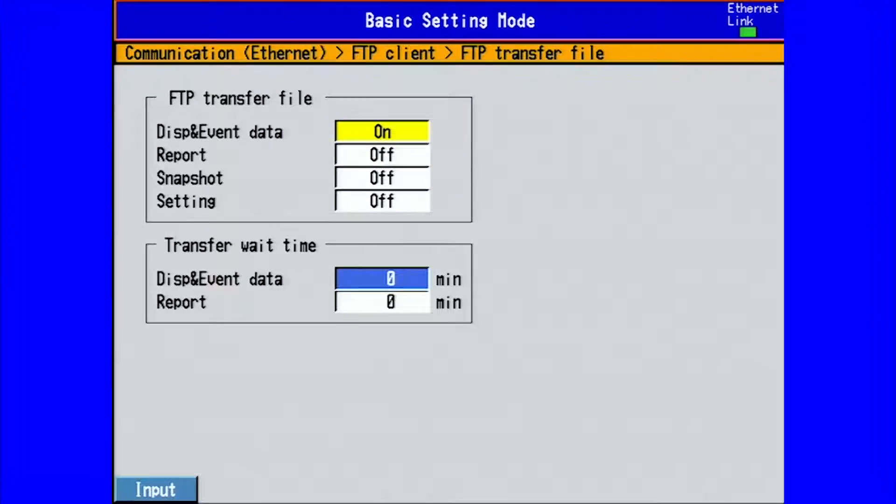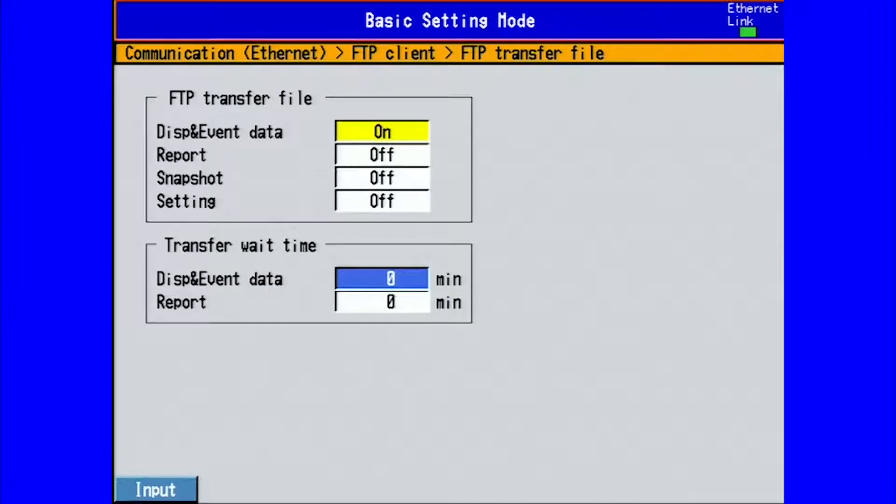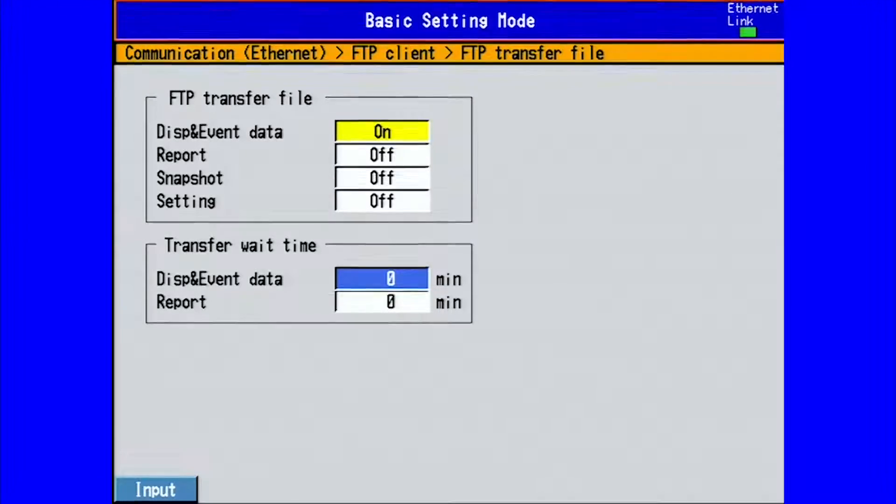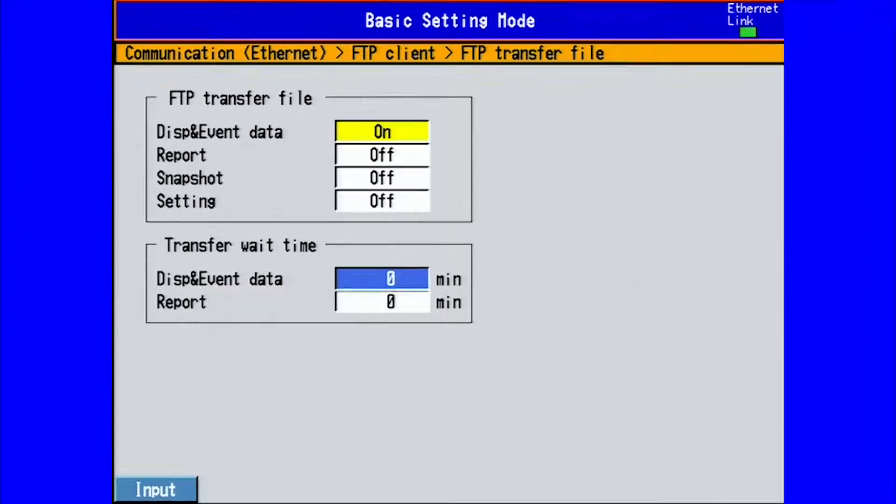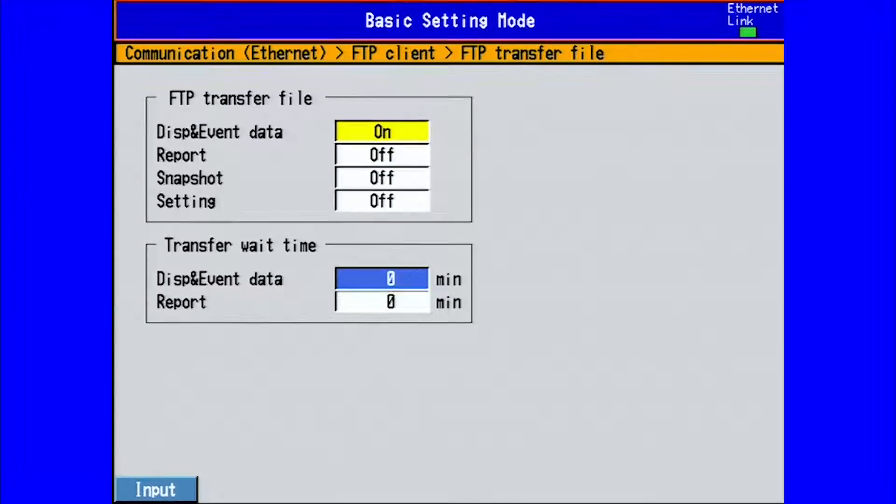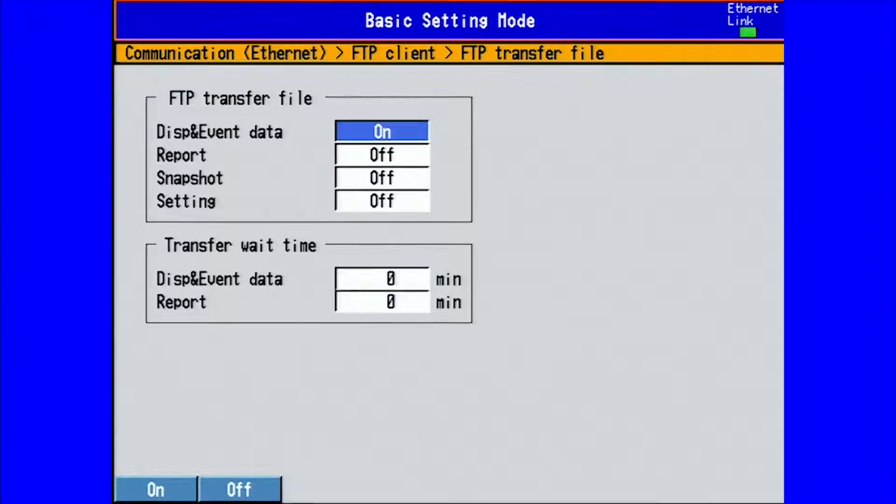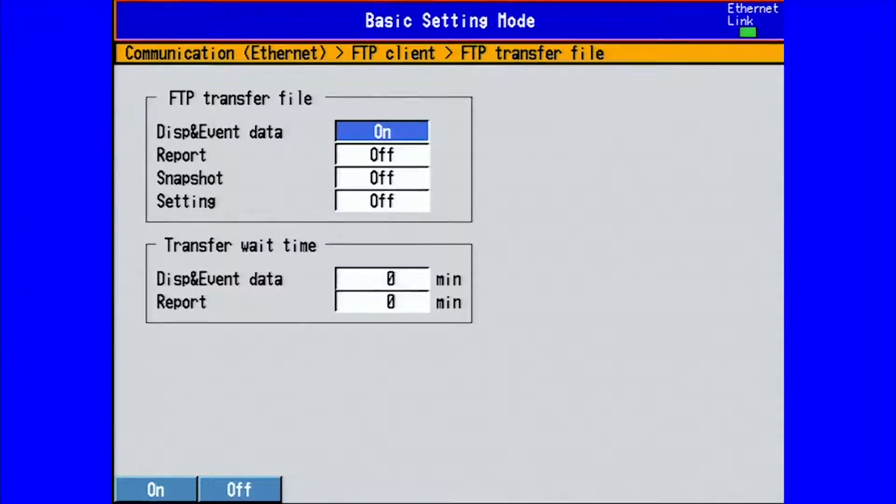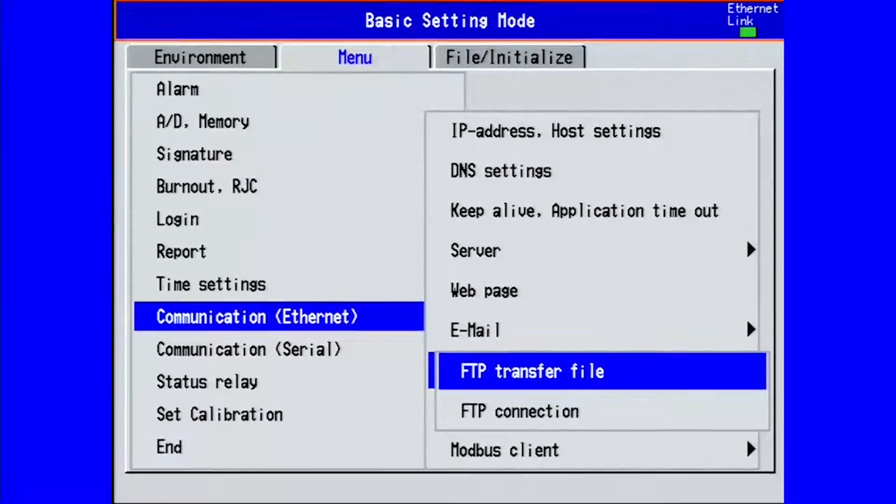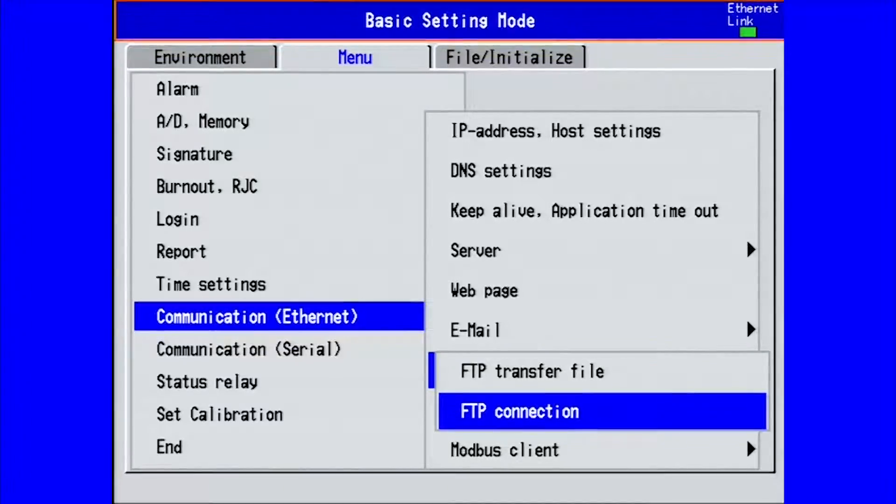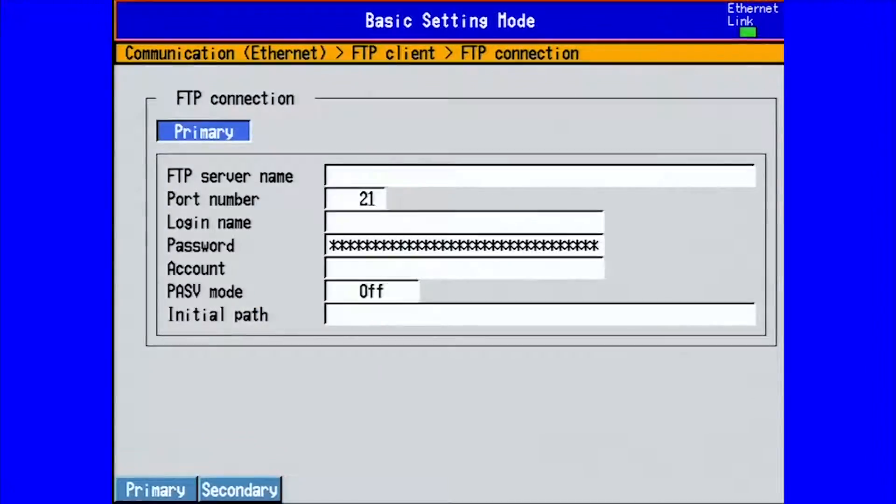Next we will look at our transfer wait time. This is how long it takes for the recorder to send the file through FTP after the data file has been closed out. By leaving at zero, then the data file will be sent immediately once closed. If we're done making our settings, we press enter and then escape. Now we go to our FTP connection settings and press enter.